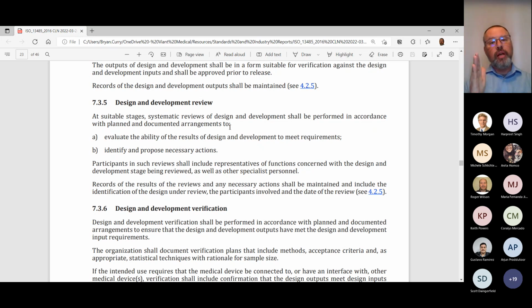So a lot of times what we'll do in design reviews is we will break it down and say, here are the elements of the design that have already satisfied everything up through, call it design inputs. And here are the elements that are still undergoing design inputs. So we're going to give conditional approval for these activities to continue into design outputs, but we're going to hold the design at design inputs until these elements over here catch up to where we're at.